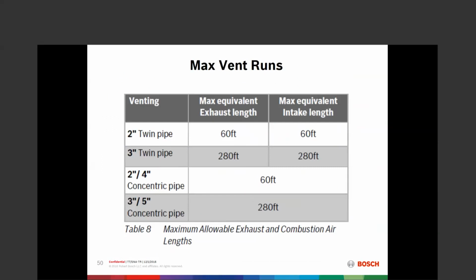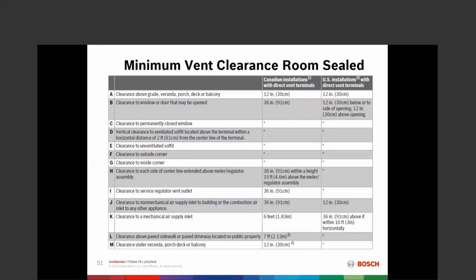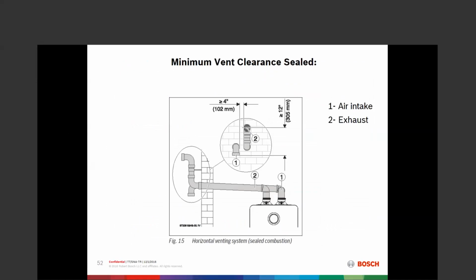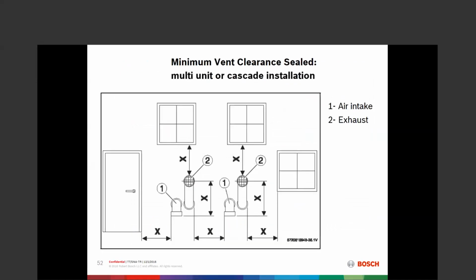That's the equivalency. And if you think about 60 feet, even if you throw 6 elbows into an exhaust, those 6 elbows eat up 30 feet. You still have 30 feet of straight pipe to get the exhaust out, and then another 60 feet equivalency to get the fresh air in. 12-inch clearance is pretty standard. 12 inches between the intake and the exhaust. It'd be 12 inches above ground or snow line. 12 inches from windows and doors when we are a twin tube or sealed combustion exhaust. And again, that's a minimum. More is better. If you can get more, that's better, but at least 12 inches there.